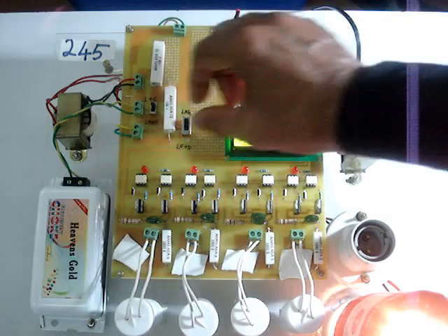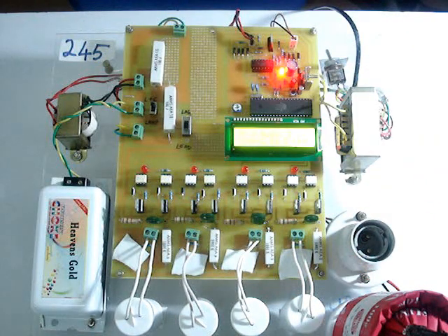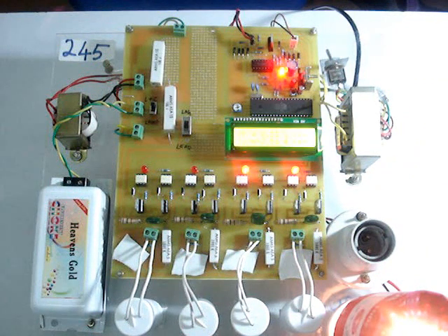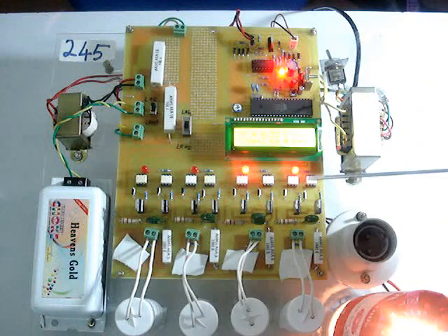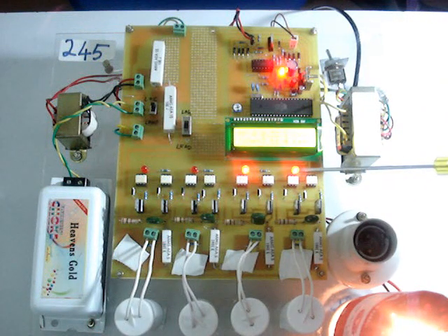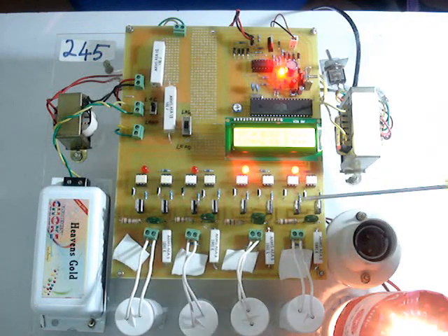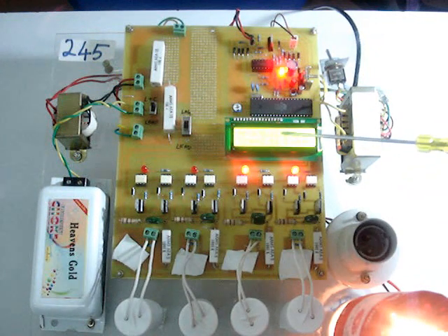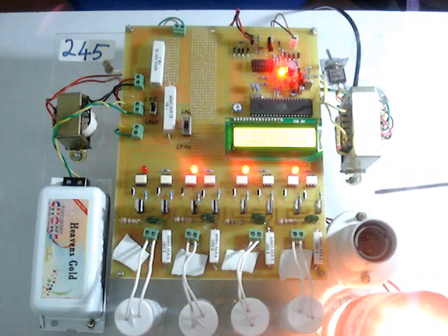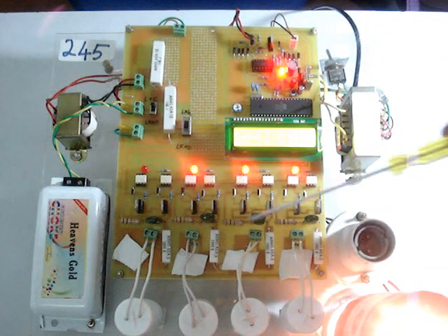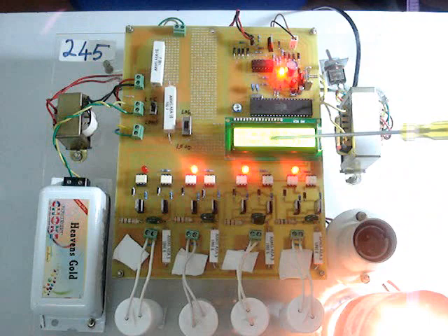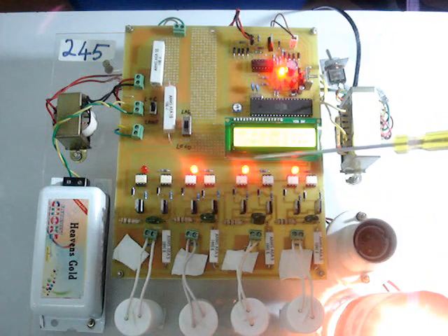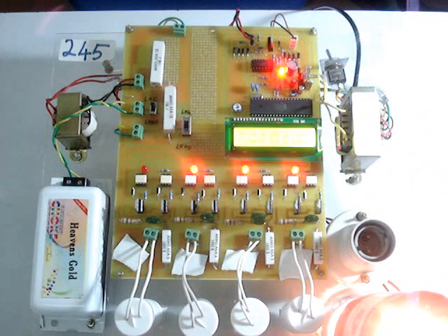Now once we change over to the leading mode, it indicates the leading power factor, where there are two capacitors: one capacitor for this back-to-back SCR and another capacitor for this back-to-back SCR, and that's how we get 0.61 lead. We have programmed it in such a way that it goes on switching one capacitor after another in parallel, so that we find how much the leading takes place. After 1 it went to 2, then 3, now about 0.8 lead, and the time shown is about 1 to 2 milliseconds as far as the leading time is concerned.